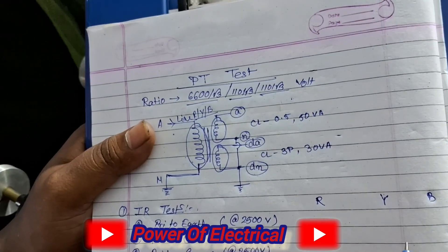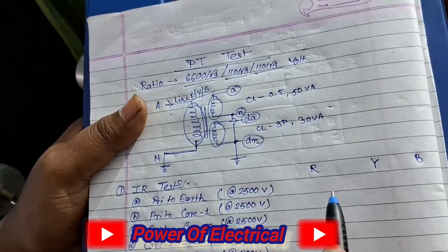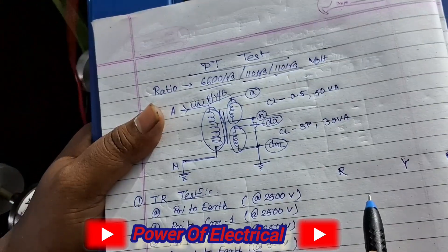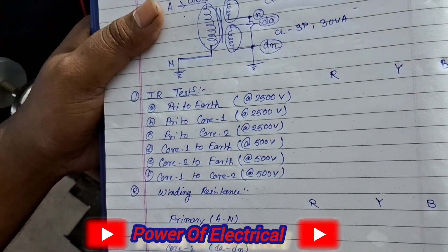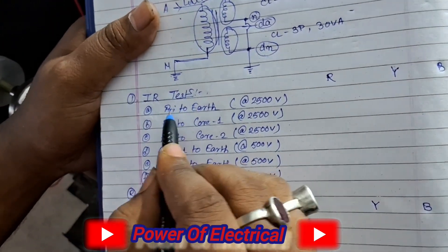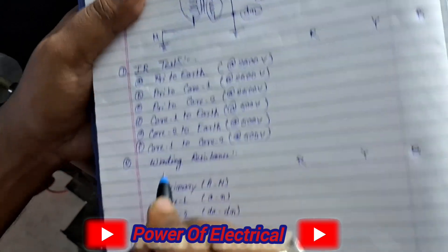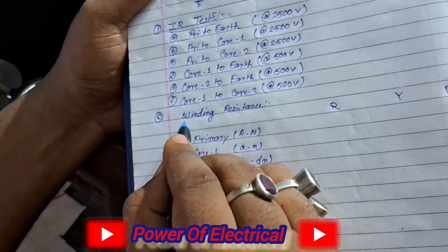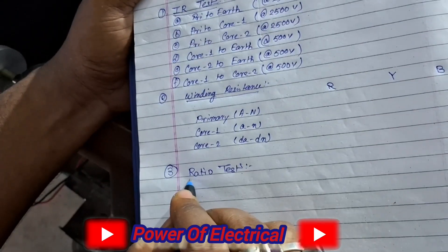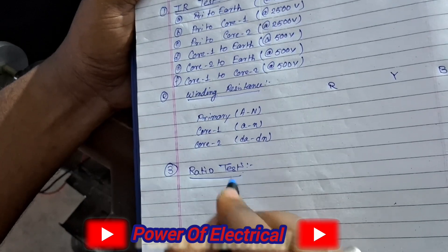In the substation or power plant, we have some pre-commissioning tests for the PT. We have three pre-commissioning tests: first is the IR test, second is the winding resistance test, and third is the ratio test.